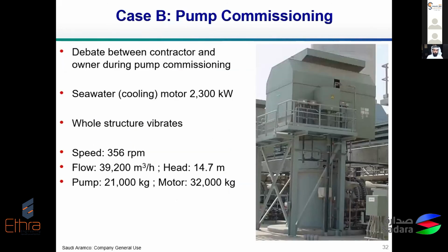So I will conclude by having one short case study. This is a large machine that was under commissioning, and during this case, the VMS was not fully commissioned, and we were requested to have data collected by portable data collectors. And this machine was running at very low speed, around 360 RPM, which is around 6 hertz, I guess.